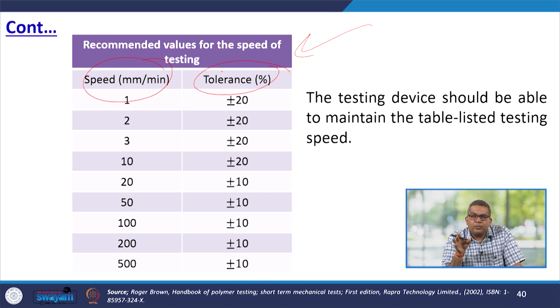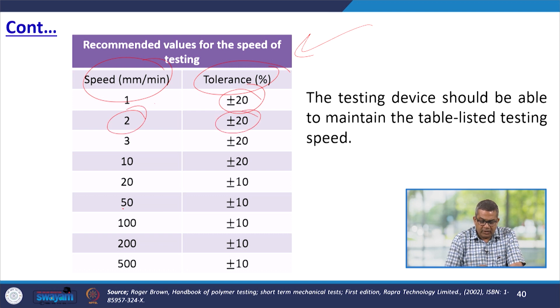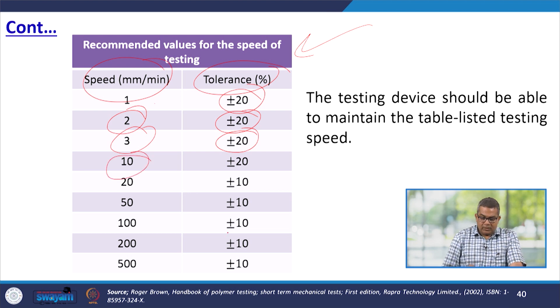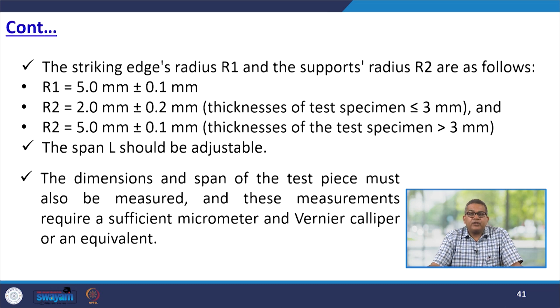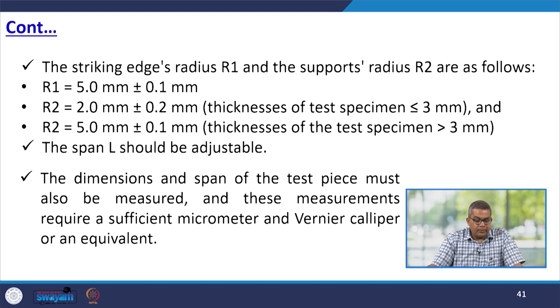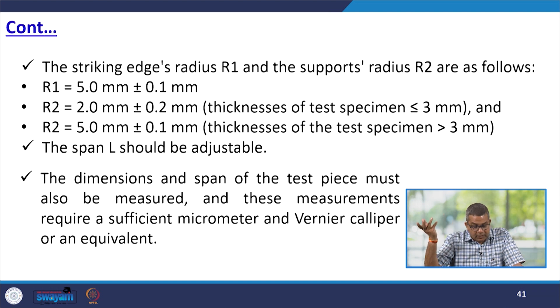The test device should be able to maintain the recommended testing speeds: 1 mm/min ± 20%, 2 mm/min ± 20%, and 3 mm/min ± 20%. At higher speeds of 50 mm/min and up to 500 mm/min, a tolerance of ± 10% should apply. The striking edge radius R1 must be 5 ± 0.1 mm. The support radius R2 must be 2 ± 0.2 mm for specimen thickness ≤ 3 mm, or 5 ± 0.1 mm for specimen thickness > 3 mm. The span L should be adjustable. The dimensions and span of the test piece must be measured using a suitable micrometer and vernier caliper or equivalent.